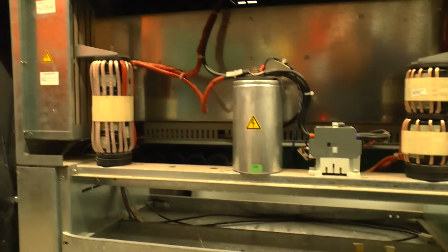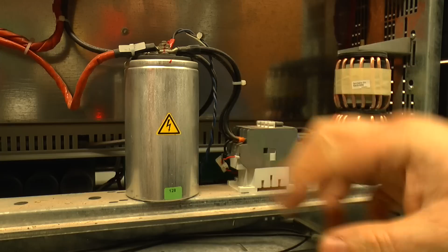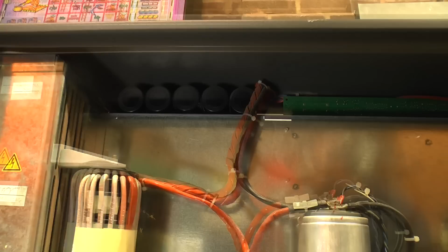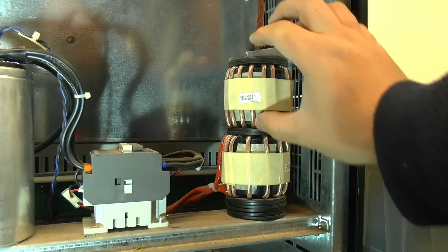So what have we got here? Well, there's a massive capacitor in the middle there, which has been discharged for a long time. That's rated at 400 volts DC, 250 volts AC, 200 microfarads. And there's a big contactor here as well, taking the power through to the other side. There's connections going across the top as well. We can just see there's a bank of capacitors up there. This strange contraption has a whole load of ferrite cores in there, and over here we have a similar setup with fewer cores, and there's two of them, but they're mounted on one of these. Again, they're mounted in the same format as the other one.